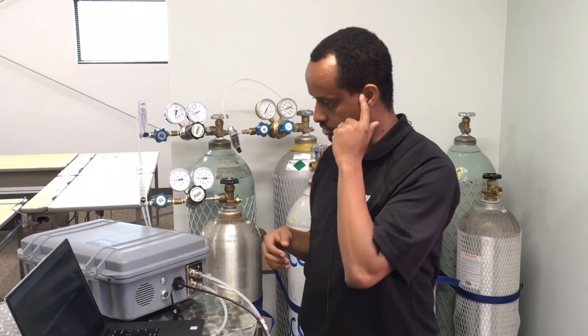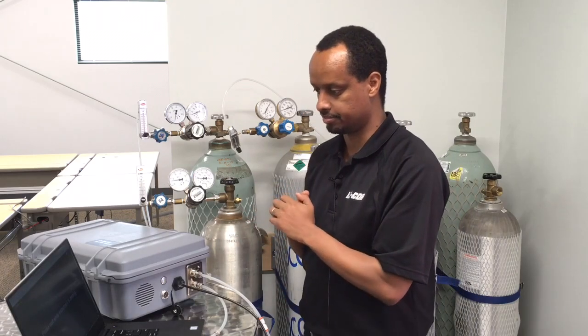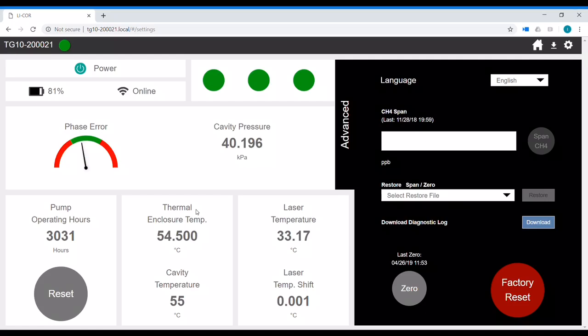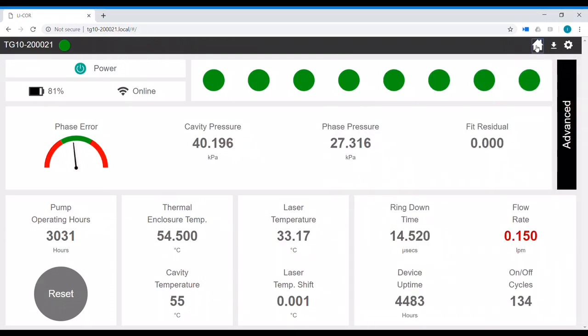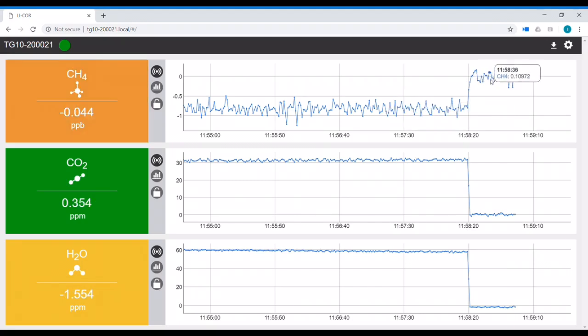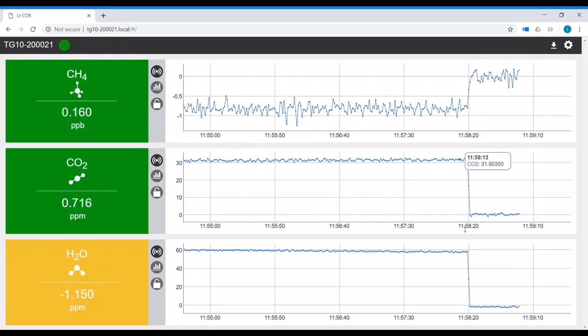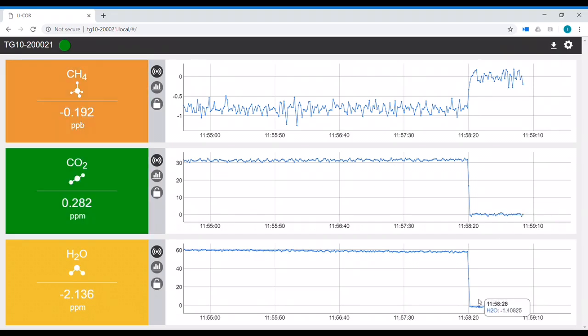So while the instrument is zeroing, we'll go ahead and get our span tank ready. So the zero process is done, and it takes us to the screen we were on. You can see the last zero is the date we did it today, and so we can go back to the home page and look at the readings. So now the methane reading is hovering around 0, the CO2 reading is also hovering around 0, and the water reading is also hovering around 0. So all of the gases are reading 0. So the zero procedure that we do is for all 3 gases.